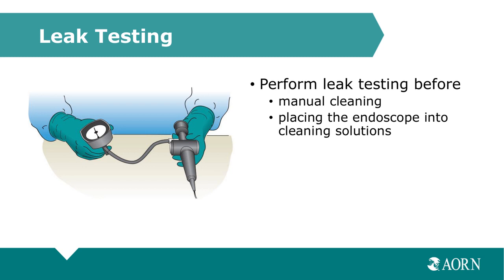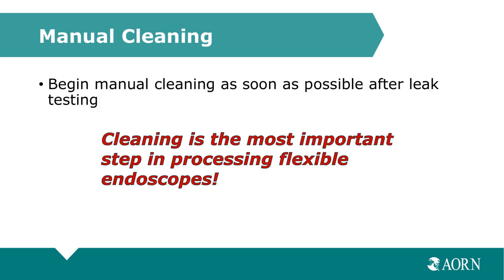Leak testing detects openings in the external surfaces and the internal channels of the endoscope that could permit water or chemicals or organic material to enter portions of the endoscope that are not intended for those materials. And these materials and fluids can accumulate in the endoscope from the time the integrity of the endoscope has been breached until the time that the leak is identified.